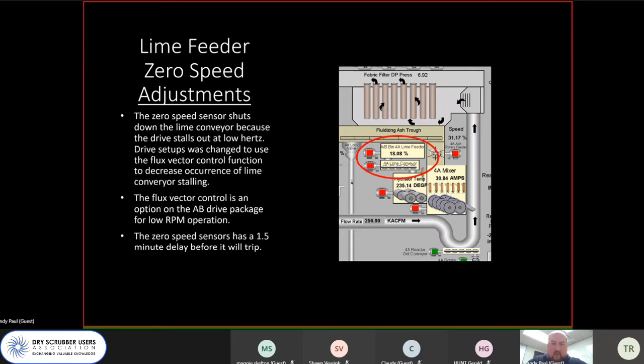Originally the speed sensor trip was 30 seconds. We've been able to increase it to a minute and a half through trial and error. And the installation of this lower RPM operating mode has really helped us to minimize our usage when we're down at low loads, which, for example, this past year for us, April, May, June, September, and parts of October, we see fairly frequent low load operation due to high wind. So it has been very helpful from a reagent reduction standpoint.